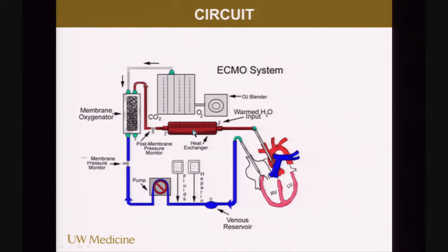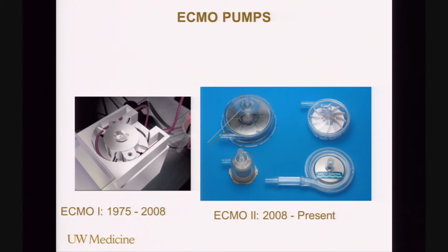So here are the pumps. The older pumps were roller pumps that got reduced to a smaller size, but they were still roller pumps, and they were still causing a lot of damage to the cells going through the tubing. These are the newer pumps. They're centrifugal pumps. They're run by a magnet. They're frictionless, and they cause, again, much less damage to cells.